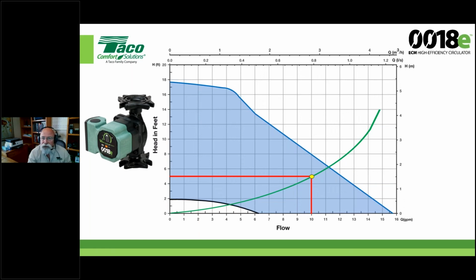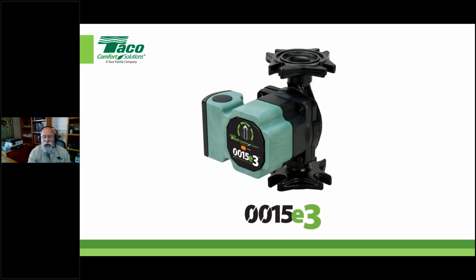So those are good. You go out on a job, you're just starting a boiler up and it's really cold, and you've got some really cold water coming back from a high mass slab. You can put that boiler in a design condition. That means the maximum firing rate it's ever going to see under a normal design condition, right? So anyway, that's what we want to try to simulate. Okay, let's say you've got a 0015 E3. It happens to be on the truck. It's midnight, and I can't turn this pump down to what it should be. Then what is the appropriate mode to use?